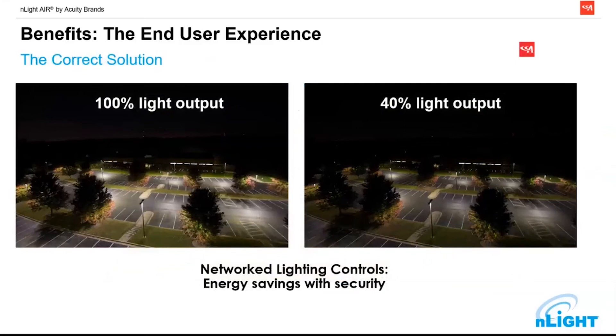That really gives us an advantage in the middle of the night. We're seeing more and more townships — there was one in New Hope, Solebury that I did recently — where the township requires that after a certain time of night or after no occupancy, fixtures have to dim down to 10%. That's very hard to do with a traditional time clock, but very easy with our nLight Air-enabled sensors. This was a retrofit application where we had lights dimmed down to 10% after two hours — just a nice little glow in the lot. Then after another 30 minutes, they could turn off completely, satisfying township requirements. They also had a master photo cell to turn them off in the morning.